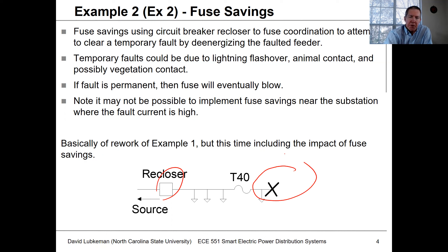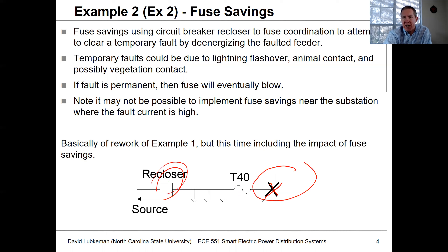If the fault at a location turns out to be temporary, instead of having the fuse act too quickly and clear the fault right away, we use a slower fuse and let the upstream reclosing action of the breaker clear that fault instead. The number of clearing attempts to remove a temporary fault is referred to as a 'shot' — that's the terminology used.